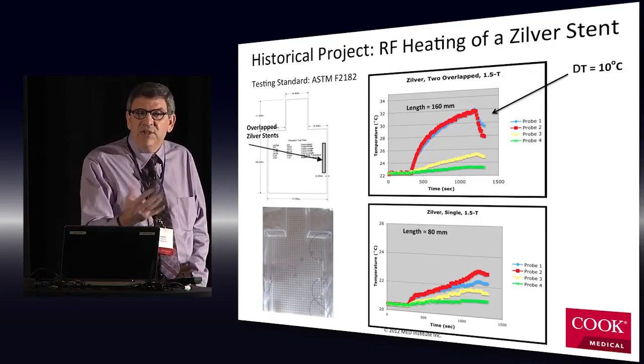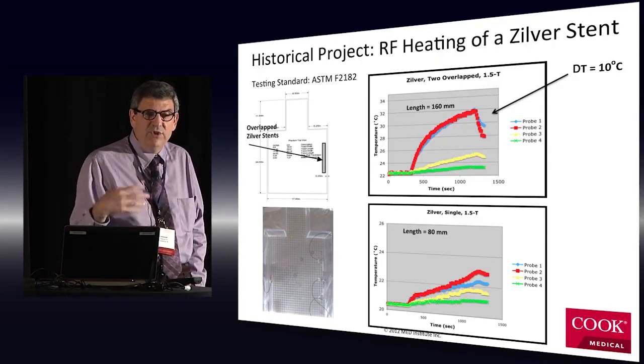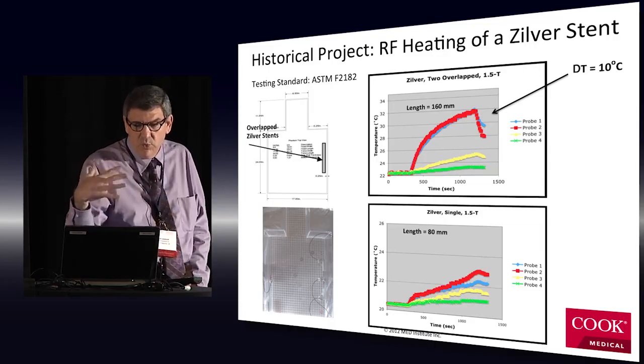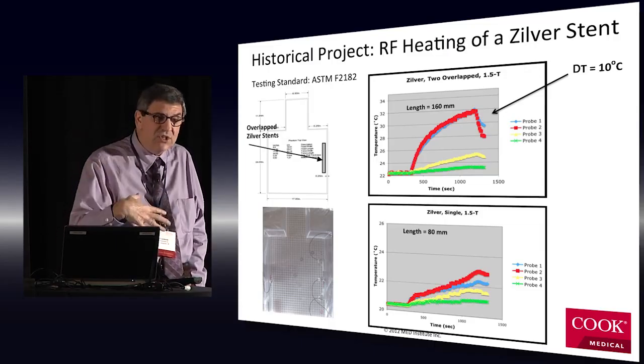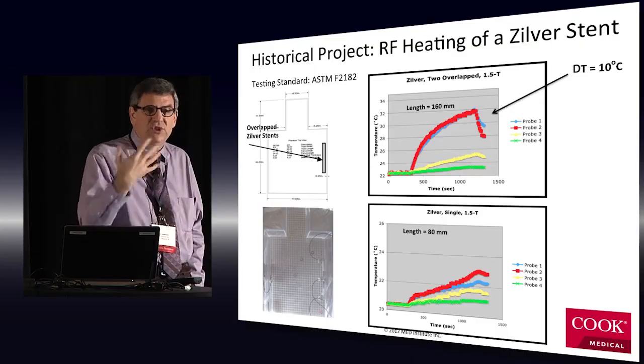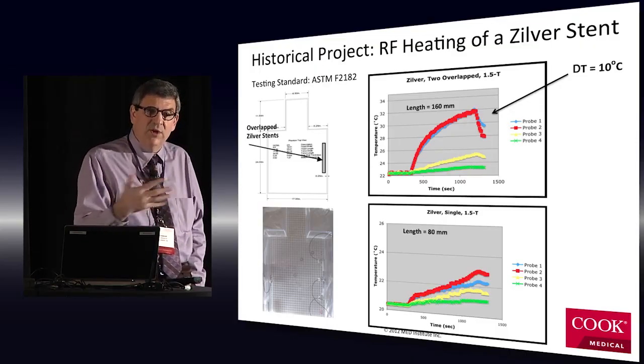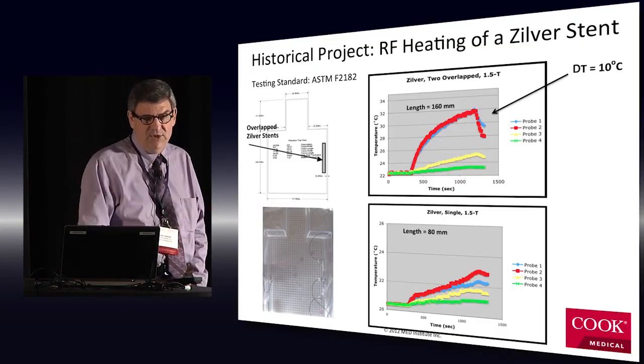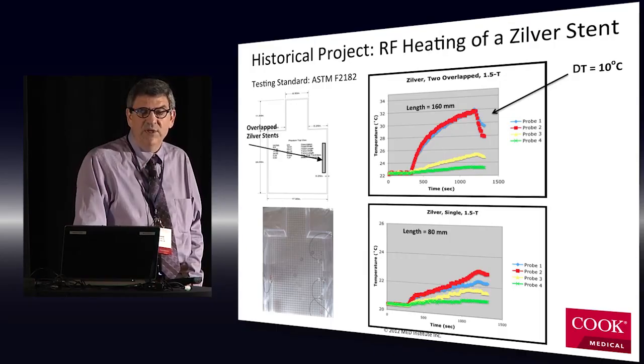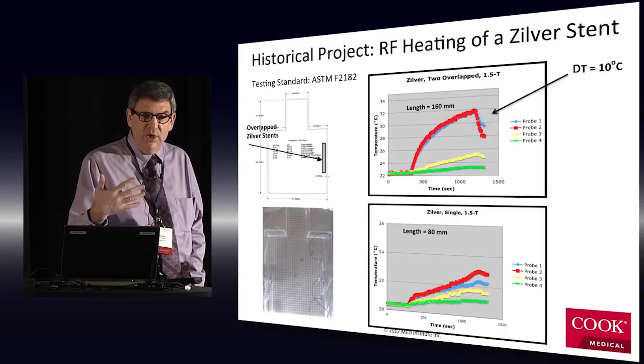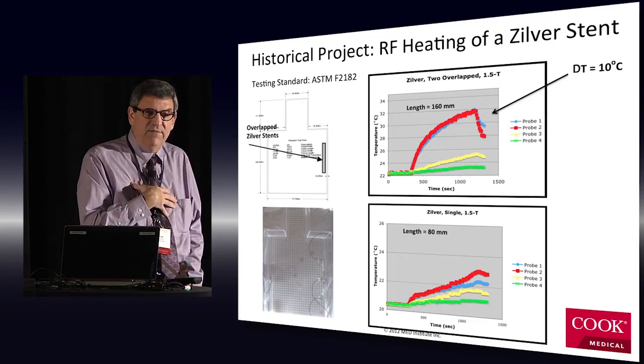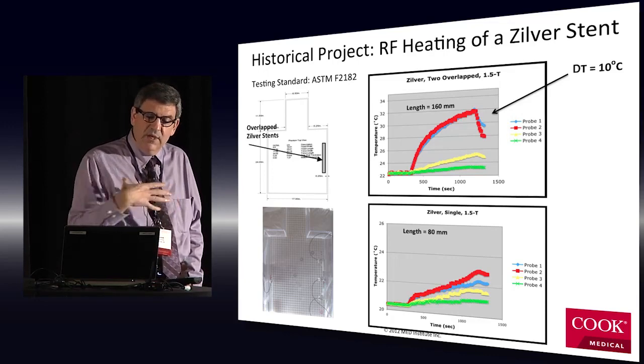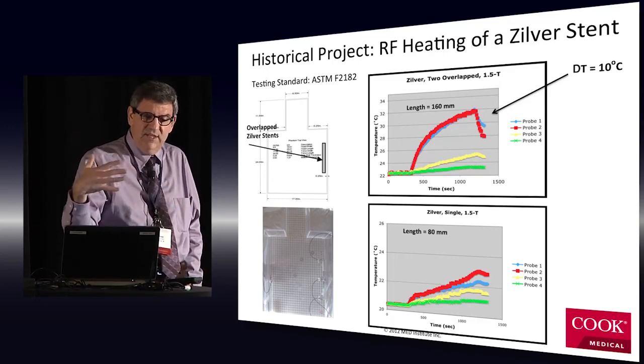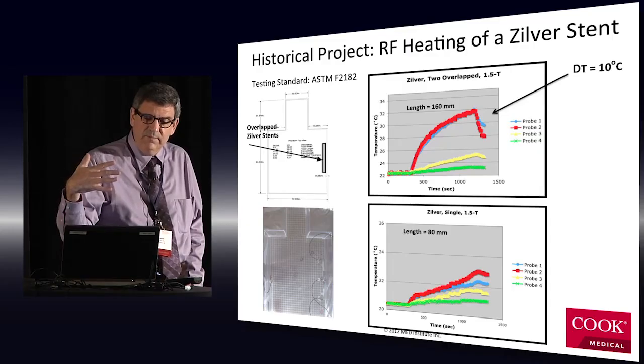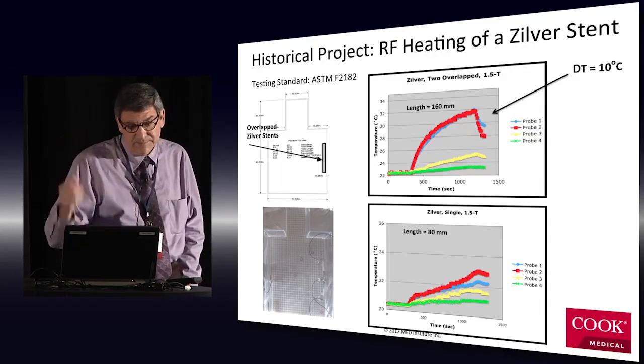And the biomedical engineers can talk to this better, but if you expose tissue to temperatures, we generally like to see things under 6 degrees, but if you get over 6 degrees, depending on the kind of tissue you are and the length of time, you can do damage. Okay? You can do potentially permanent damage. So it behooves us as a device manufacturer to understand that this is the case and then try to design devices that don't show this kind of heating.